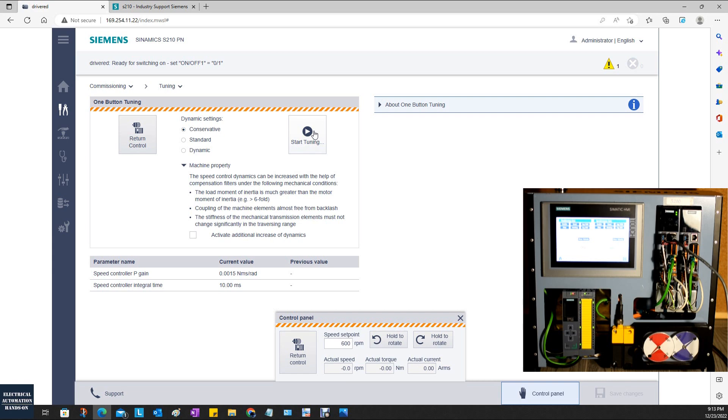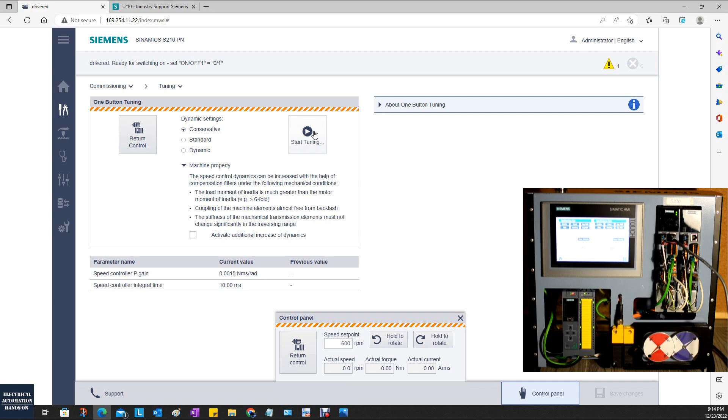After we click auto tuning, there will be one option to let us set the distance the drive will travel. You can set as long as you can, but you need to be very careful about the travel distance in your system. The longer the better, because the longer calculation could better identify the motor and your load to calculate a set of proper parameters. We need to move the motor as much as it can.